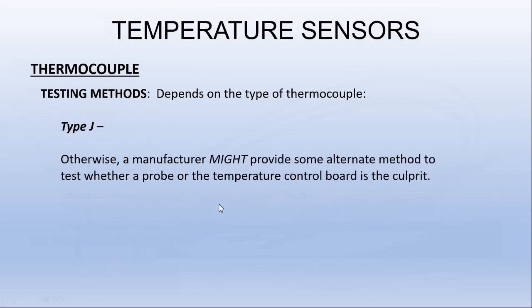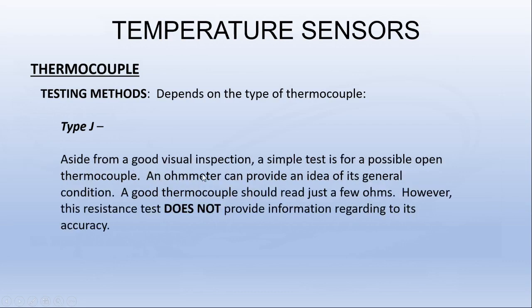Otherwise, the manufacturer might provide some alternate method to test whether a probe or the temperature control board is the culprit. Aside from a good visual inspection, then, a simple test is for a possible open thermocouple. An ohmmeter can provide an idea of the probe's general condition. A good thermocouple should read just a few ohms. Otherwise, if it reads open, then it probably is indeed bad. However, this resistance test does not provide information regarding the probe's accuracy.